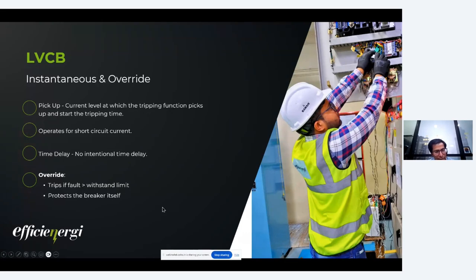Then there is an override feature available in the breaker. That is basically to protect the breaker itself, because when we set a short time pickup, in some breakers we can disable the instantaneous. Those breakers are Class B as classified per the IEC. That means they can withstand, let's say, 0.5 seconds up to the breaking capacity of the breaker. But for some breakers it is not possible, so there they give the override function in the breaker. I will explain this particularly in the short circuit withstand duty of the breakers.